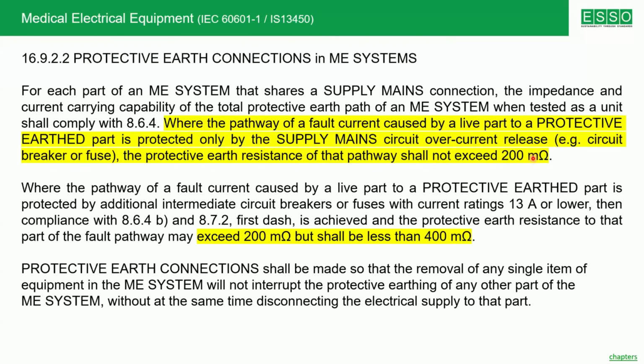200 milliohm is the resistance required for a certain application. Now, in another application, part of the fault pathway may exceed 200 milliohm, but shall be less than 400 milliohm. So there is always a requirement of maximum resistance for the particular equipment, depending upon the type of equipment we are using, as well as the power requirement for the particular medical equipment. So these are the subjects of IEC 60601.